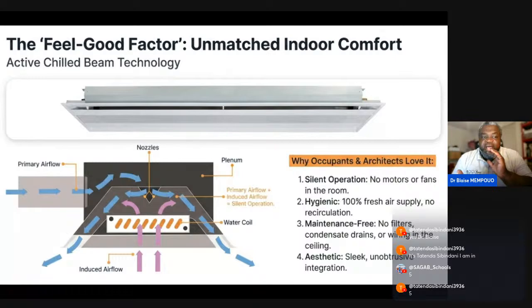Here is the active chilled beam technology. It can be active chilled beam for cooling or heating, both. As you can see, it's really silent because you rely on water instead of refrigerant inside the building, so we have no motor, no fan indoors.